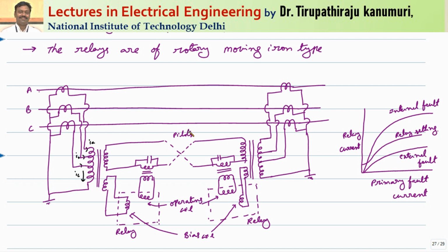Let us see how the relay operates. Here you can see on the secondary side of the transformer there are two windings. One winding is connected to the bias coil and the other winding is connected to the operating coil through a coupling transformer, an isolation transformer. One capacitor is connected across this transformer. The purpose of this capacitor is to tune the circuit so that only your supply frequency component is transferred to the operating coil and the remaining components are bypassed through the capacitor. So it is tuned only to the 50 Hz component. Only the 50 Hz component will pass through the operating coil, and the remaining components will not pass. That is the major purpose of this.